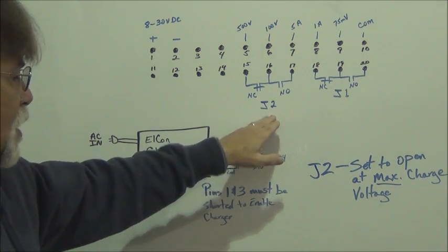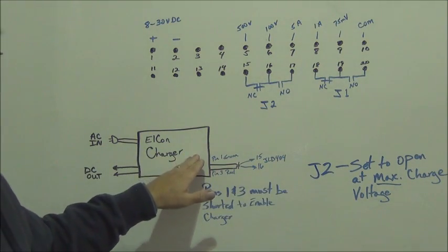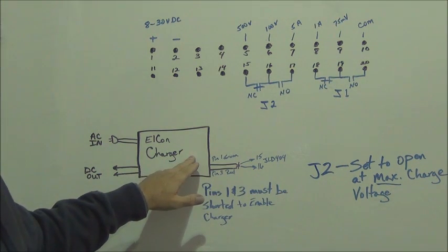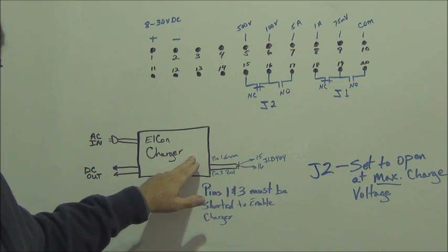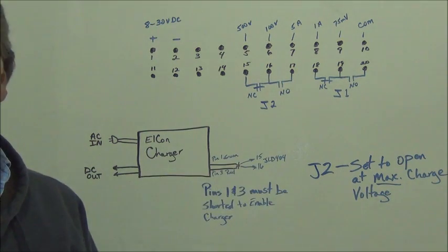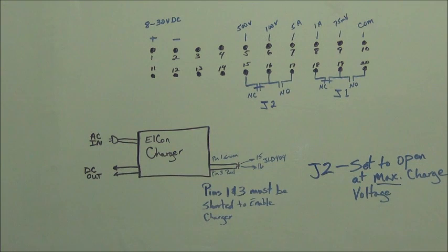We program it so that J2 will shut this off. So we have a redundancy built in. The charger internal program is going to shut it off at that specified point, and if it doesn't, our JLD-404 will.